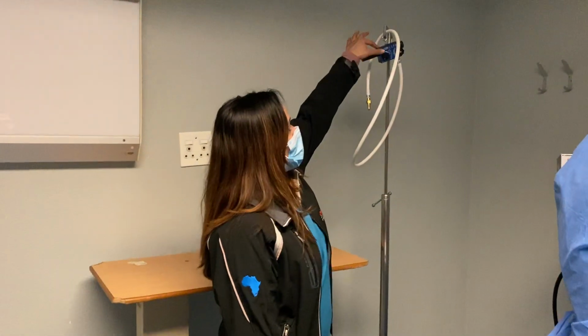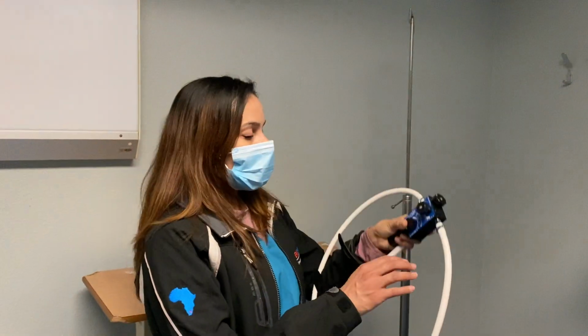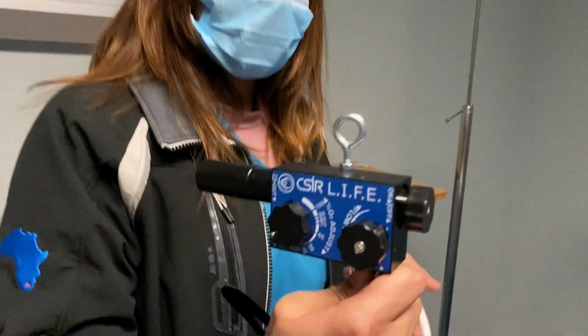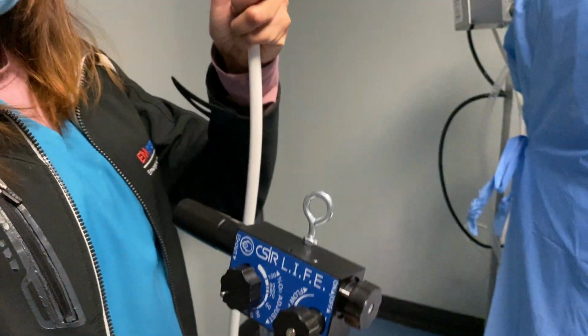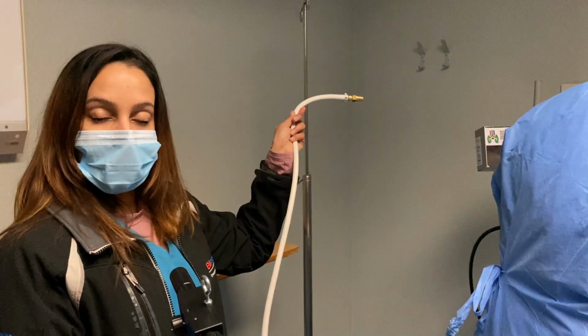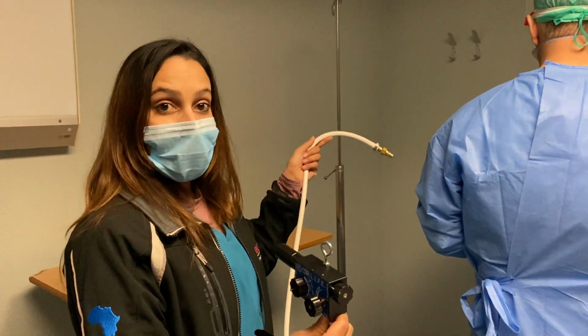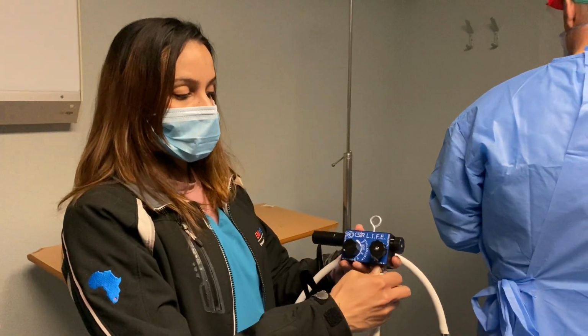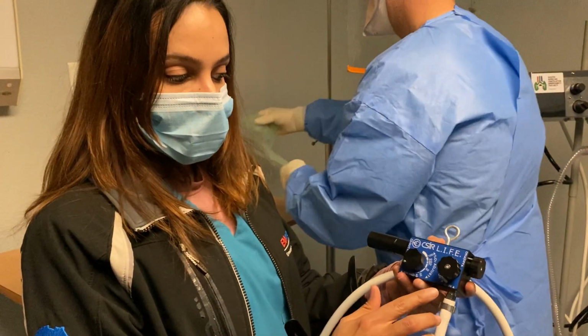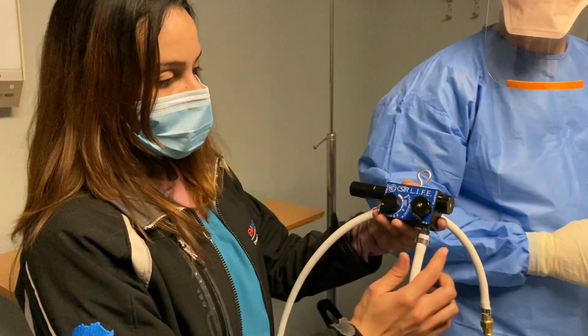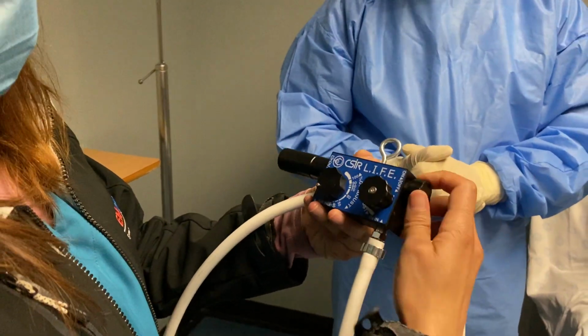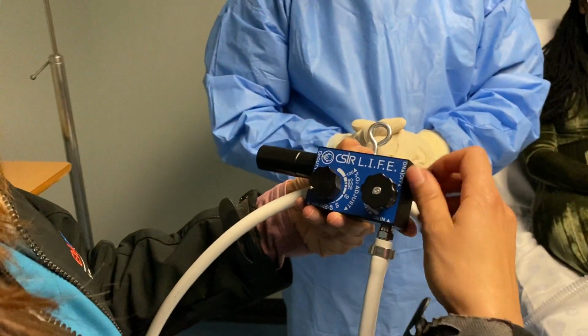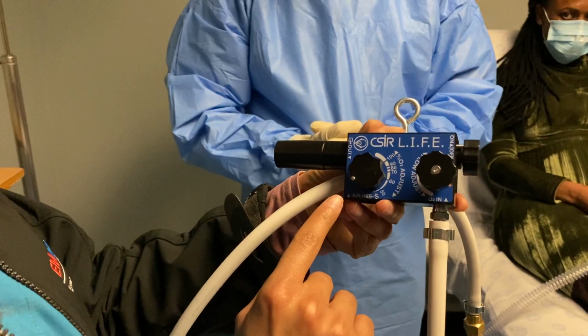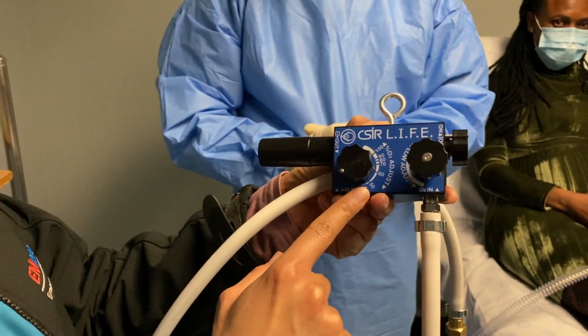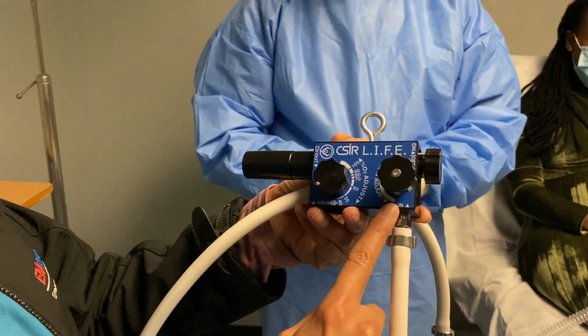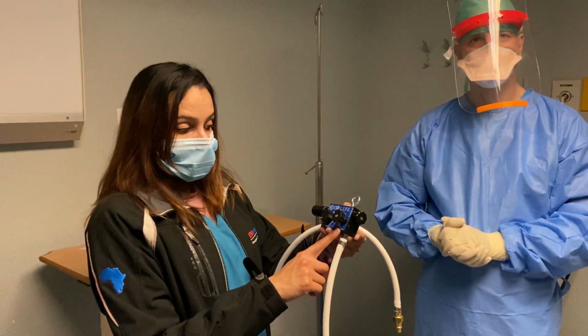So with the CSIR Life device, this device has an oxygen port, so this needs to be connected to the wall oxygen, but you will notice that there is no port for air to be connected. So what happens is that the room air is entrained into the device with the flow adjuster. So we've got 3 buttons. You can see an on-off button, which when it screws either tight, then it's off, or if it's loose, then it's on. You also have an FiO2 or percentage oxygen adjuster and your flow adjuster. So the principles are exactly the same as what Prof has mentioned already.